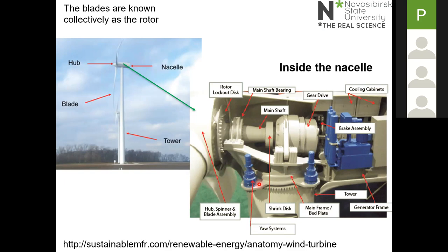The other components I want to highlight are the yaw drives — these allow the rotation of the nacelle about the tower axis so the turbine can be turned into the wind. On top of the nacelle there is an anemometer and a wind vane that give the wind speed and direction. If the rotor is not facing the wind, the yaw drive units are activated to turn the turbine into the wind.